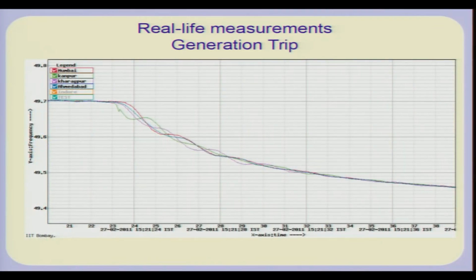So, with this we can have real life measurements, and I am going to show you a few examples of such real life measurements which have been monitored over the past several years. This is a 2011 snapshot of a generator trip, and as you see, the frequencies at various points show a swing, as I mentioned, and also an overall drop in the center of inertia motion.